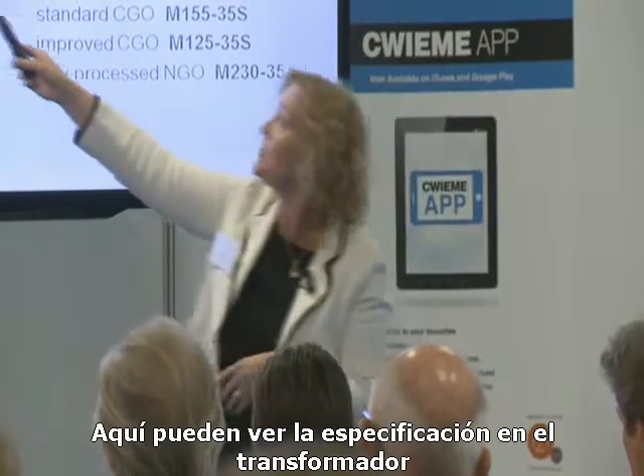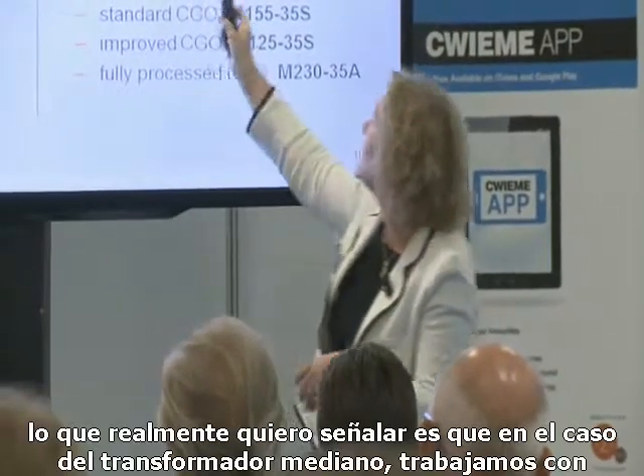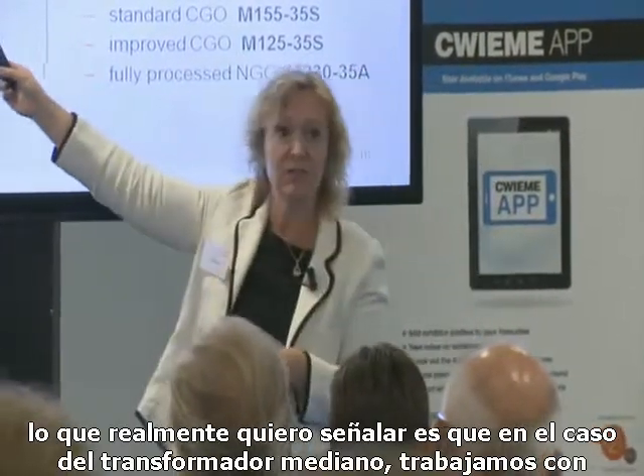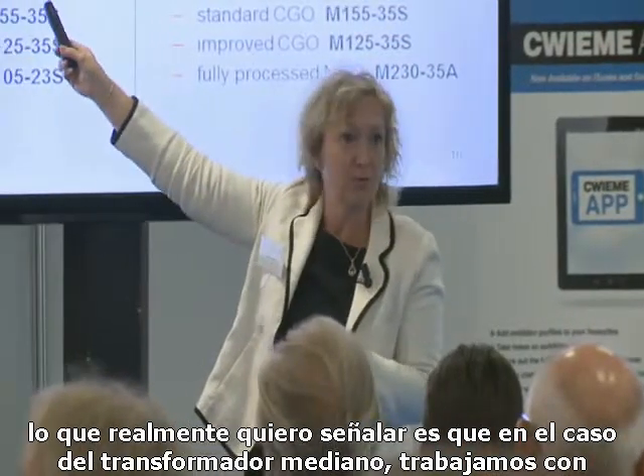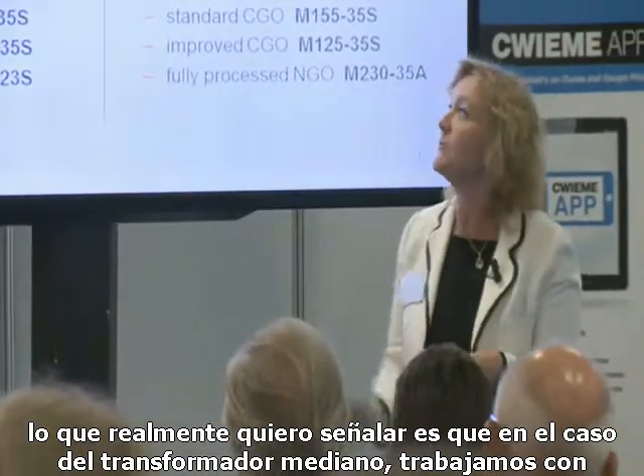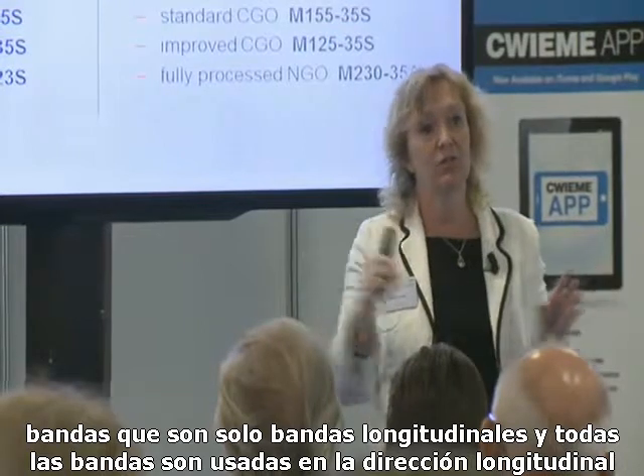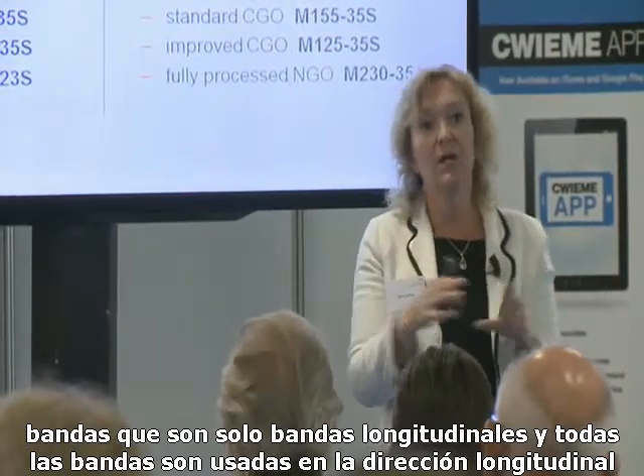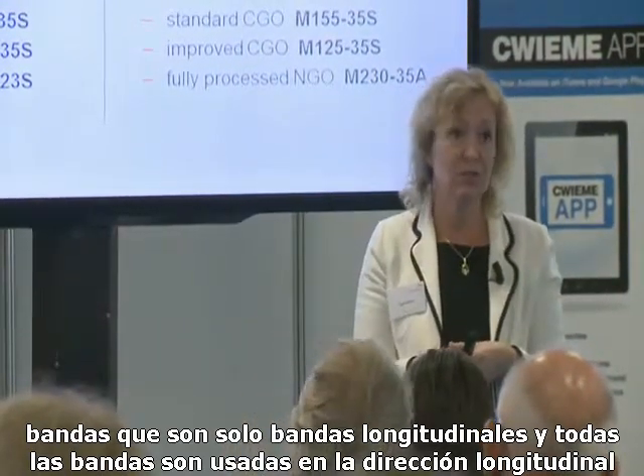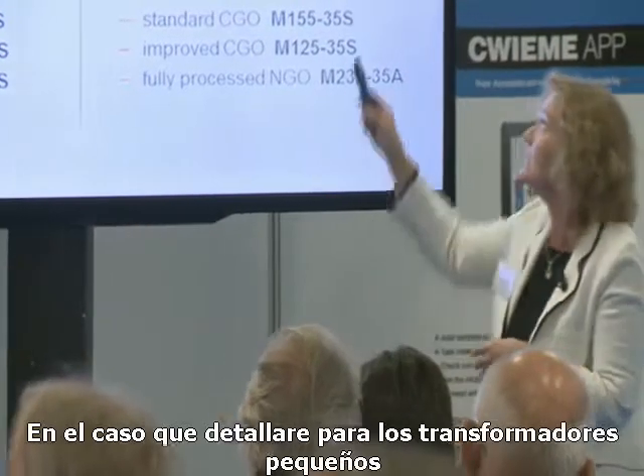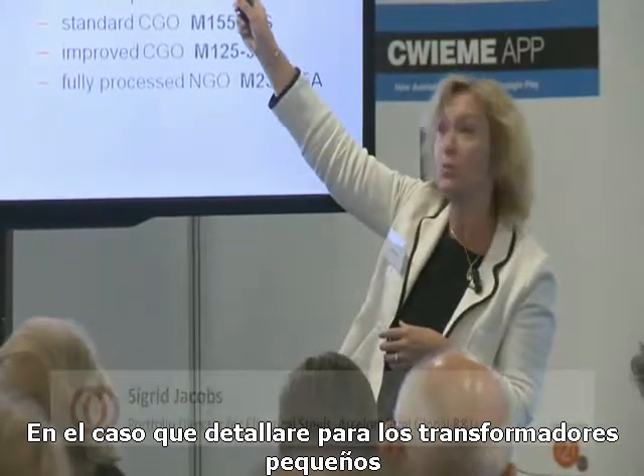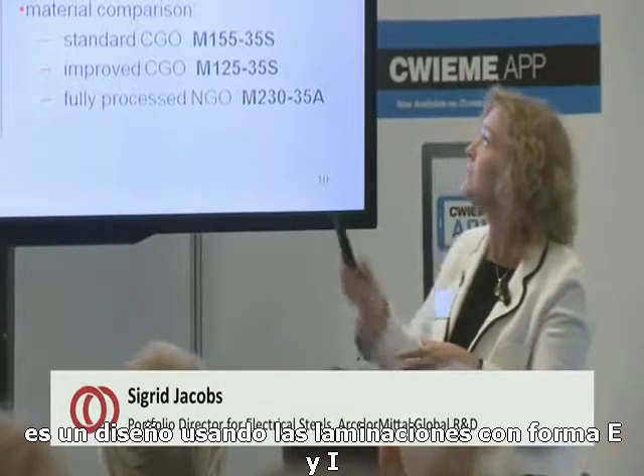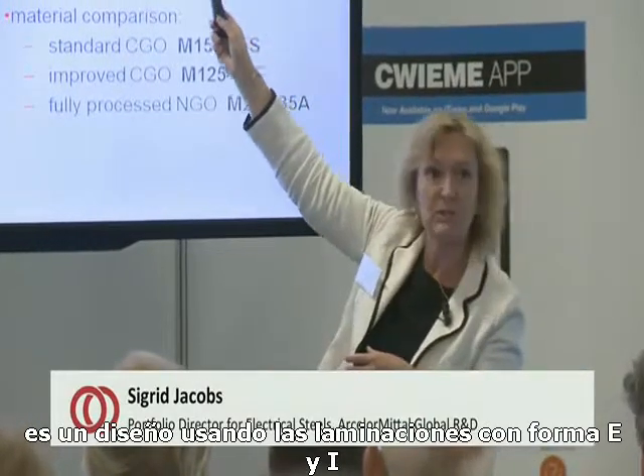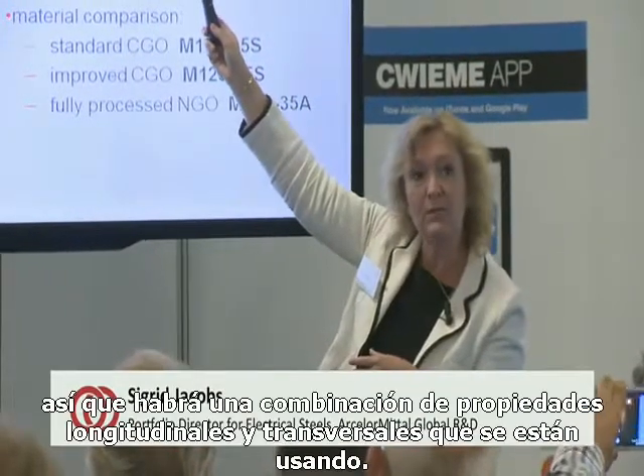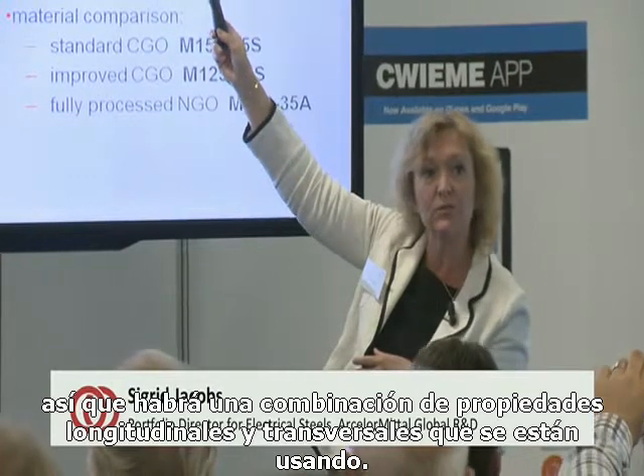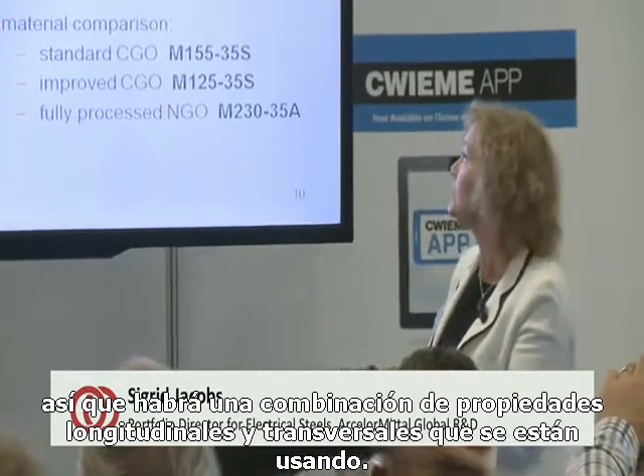You can see the specification of the transformer here. What I want to point out is that in the case of the medium power transformer, we work with strips that are just longitudinally cut, and all of the strips are used in the longitudinal direction. In the case I'll detail later for the small power transformers, it's a design using E and I shaped laminations, so there's a combination of longitudinal and transverse properties being used.